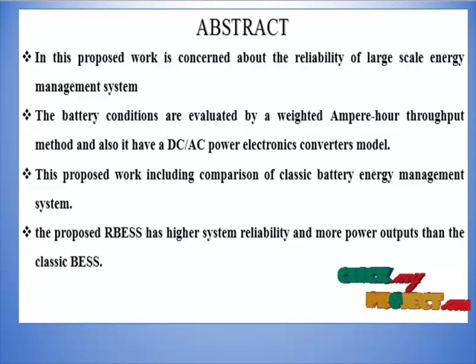The battery conditions are evaluated by a weighted ampere hour throughput method, and it also has a DC to AC power electronics converter module. This proposed work includes a comparison with the classic battery energy management system. The simulation results verify that the designed controllers can improve the control performance significantly. The comparison results show that the proposed reconfigurable battery energy storage system has higher system reliability and more power output than the classic battery energy storage system.